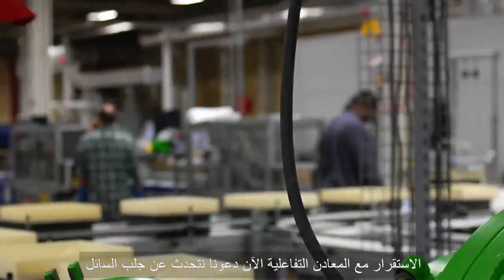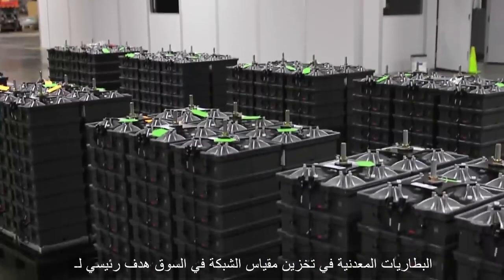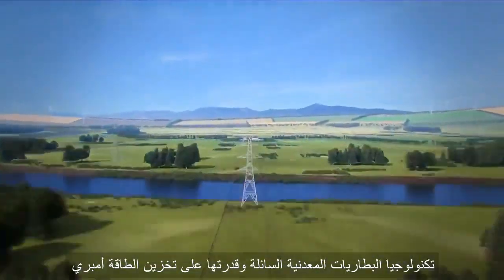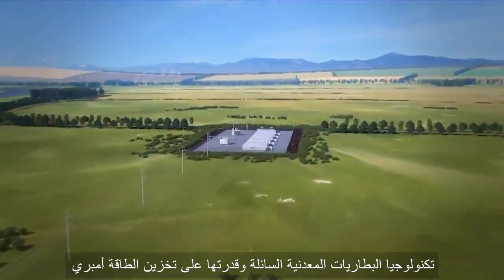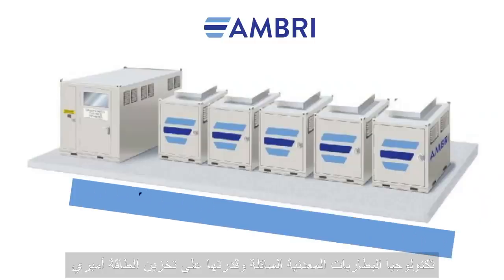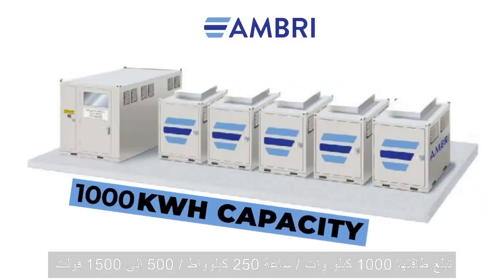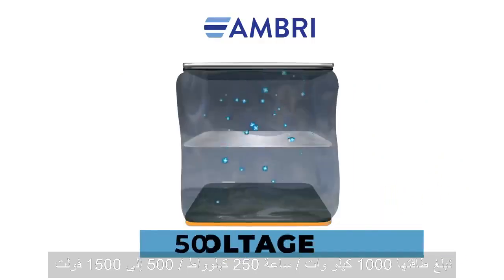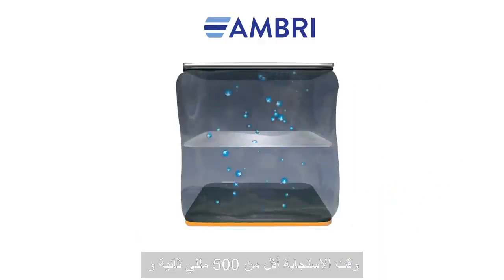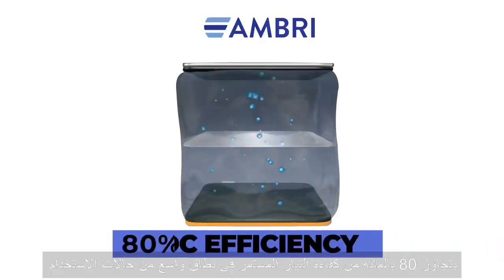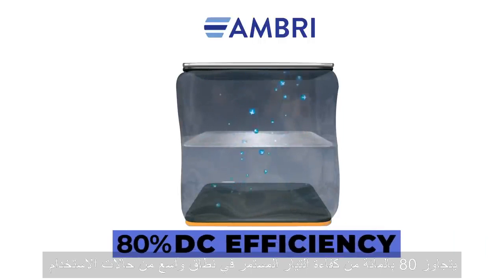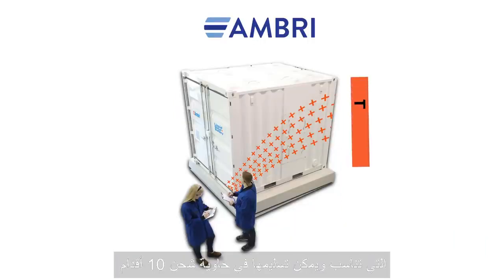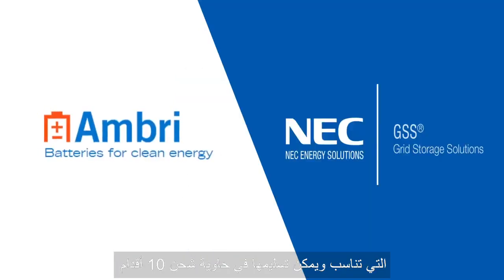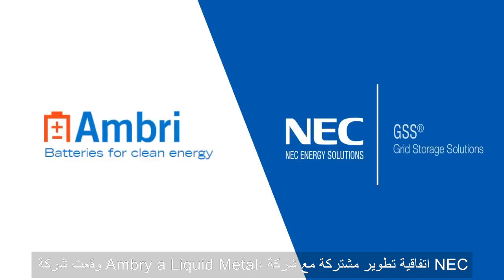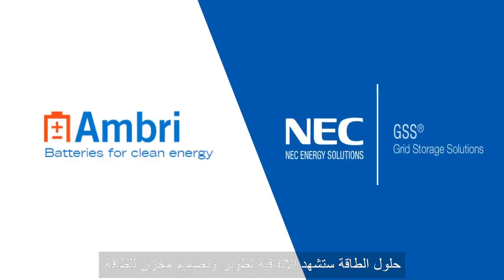Now, let's talk about bringing liquid metal batteries to the market. Grid-scale storage is a key target for liquid metal battery technology and its energy storage capacity. Ambri has a 1,000 kilowatt-hour capacity, 250 kilowatts output, 500 to 1500 voltage, response time less than 500 milliseconds, and exceeds 80% DC efficiency under a wide range of use cases, which fits into and can be delivered in a 10-foot shipping container.